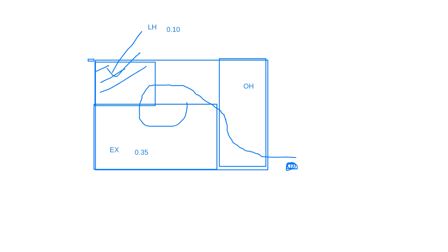Suppose you design your fire protection system for the light hazard areas, and it is protecting this one, but it is not necessary that it will protect the extra hazard area. So we need multiple sets of calculations to support our analysis, and we have to submit them to our fire protection consultant. And usually we take the highest one, the biggest one. This is the special case, you know. So in those areas we have to go something like this.